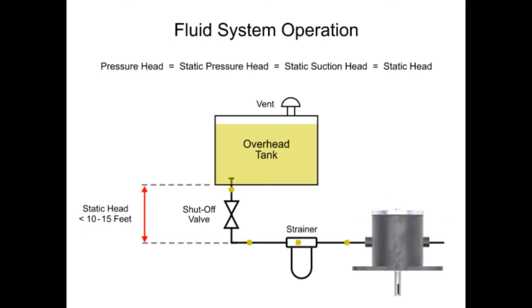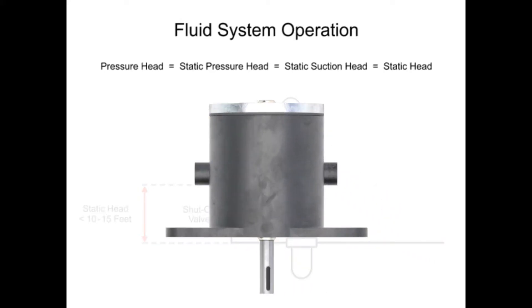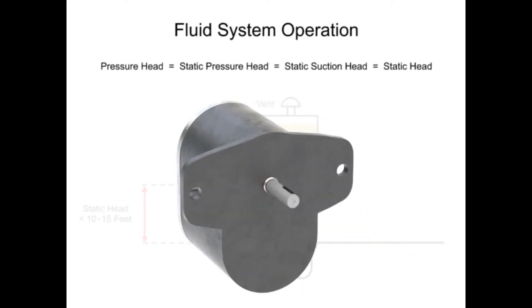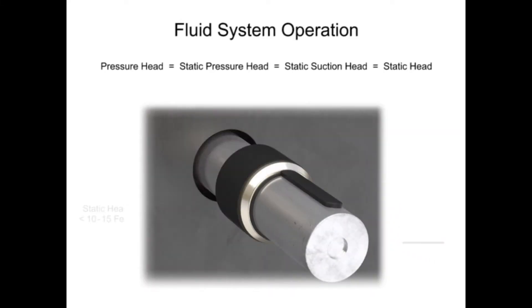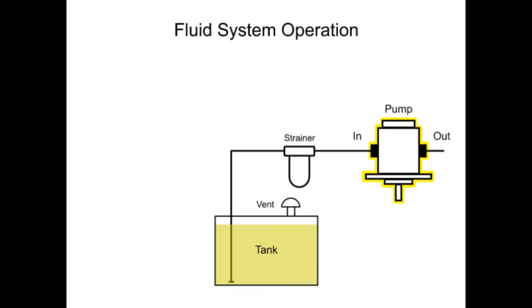If the reservoir is placed too high, the increase in inlet pressure can blow out the shaft seal of most pumps. If the pump is mounted higher than the reservoir, the height from the fluid surface to the pump inlet is called the suction head.